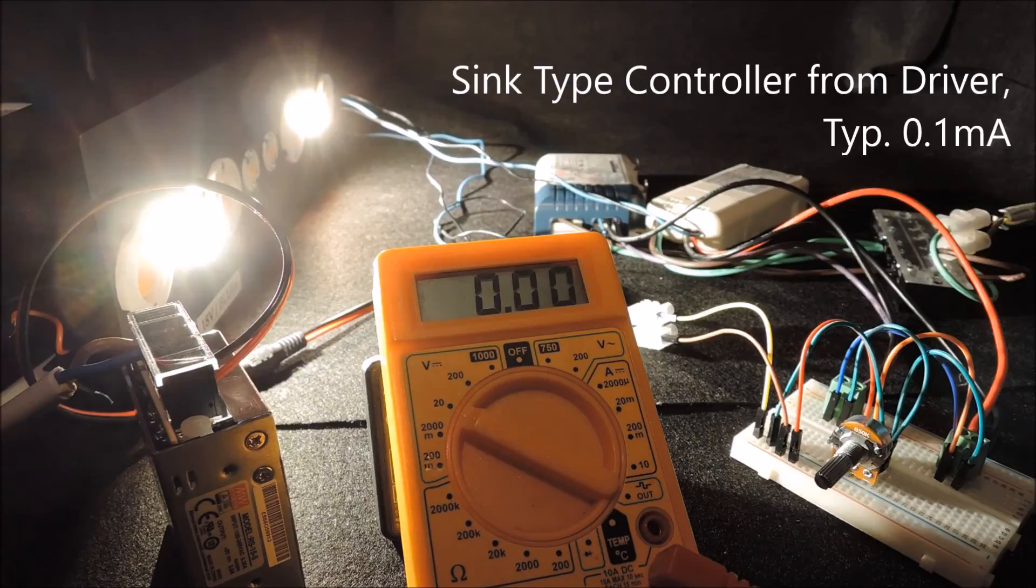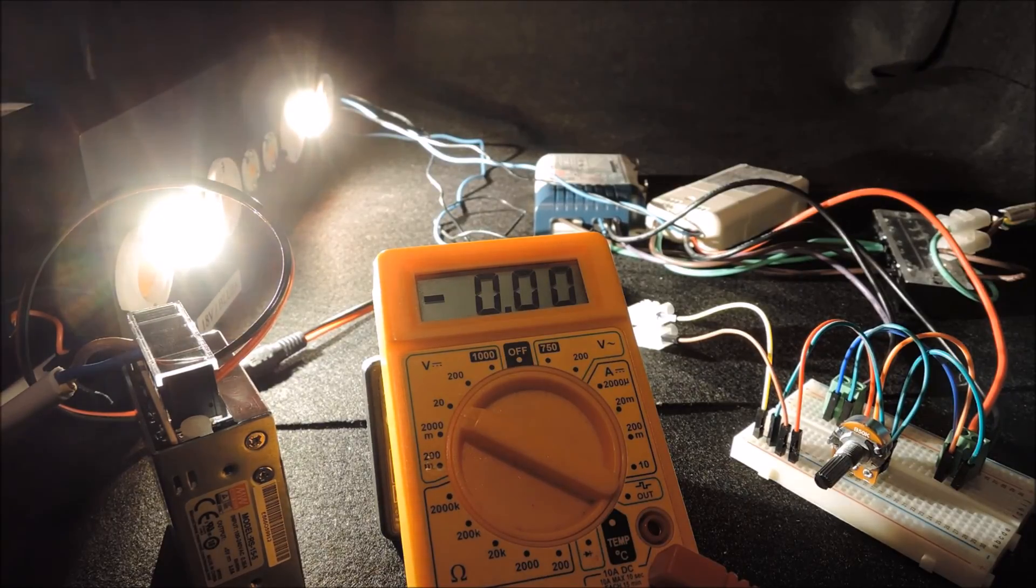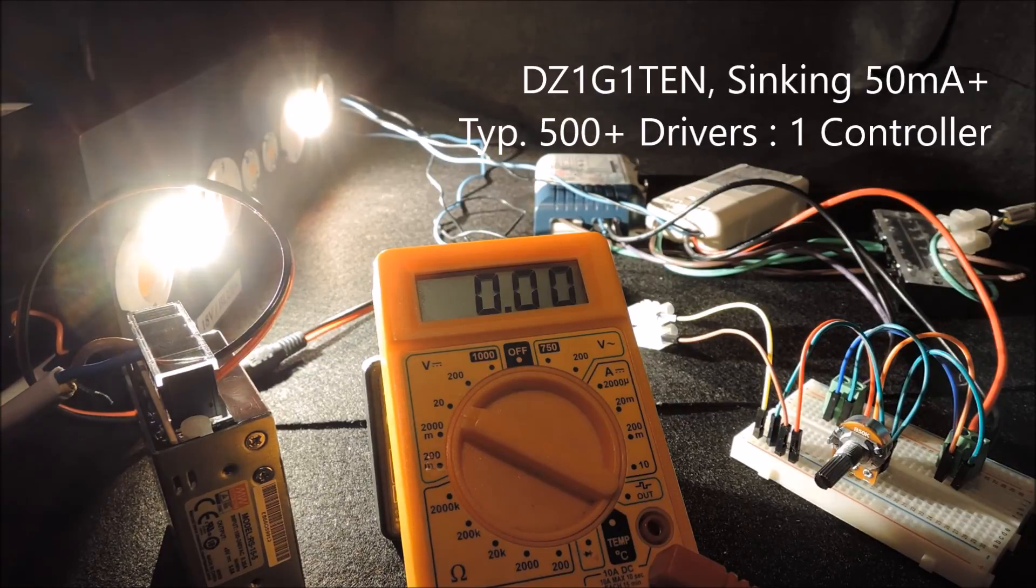A sink type device sinks a very small current from the driver, approximately in the magnitude of 0.1mA. For DZ1G1TEN, our device is capable of sinking 50mA or more, which means 500 plus drivers can be connected simultaneously to a single controller.